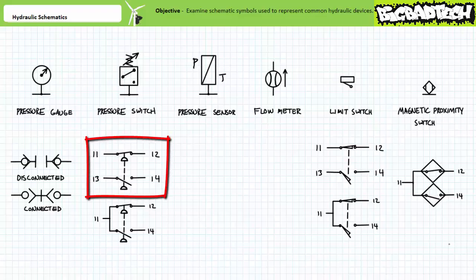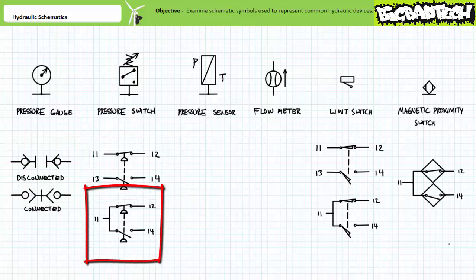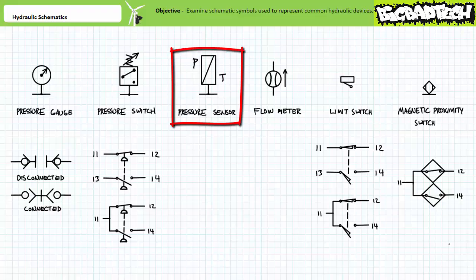Here's the electrical schematic symbol for a mechanically interlocked pair of single-pole, single-throw pressure switches, one being normally closed, the other being normally open. Alternatively, some pressure switches use single-pole double-throw transfer contacts, with both a normally closed and normally open side being serviced by a single common terminal. Pressure switches are binary in nature in that there are two clear and definite states, either open or closed. Pressure sensors, in contrast, are analog in nature. Pressure sensors measure pressure and output an electrical signal proportional to the measured quantity. Pressure sensors are sometimes indicated schematically as a box with a slash through it that says PT for pressure transducer.